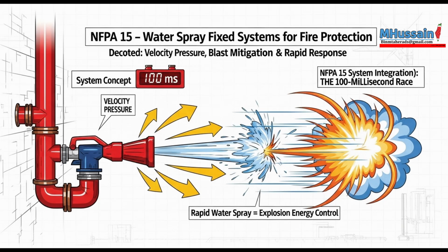Now here's an installation detail that sounds maybe minor, but in a millisecond world it must be critical. Pipe slope, 12.3.11.3. But trapped air is the absolute enemy of UHS response time. Why? What does trapped air do? An air pocket acts like a spring. It has to be compressed before the water column behind it can really start moving. Right. That compression takes time, introducing an unacceptable delay into the system.